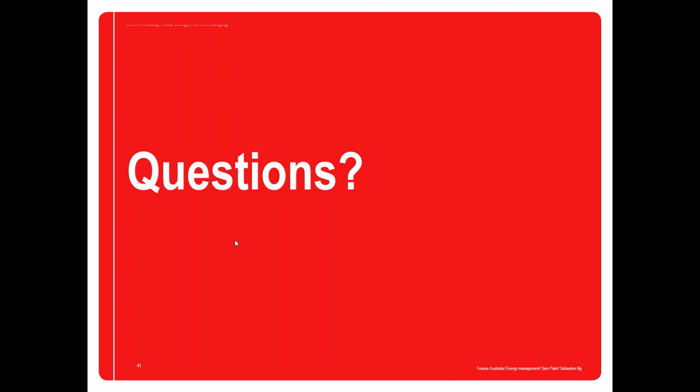It's a really good question, because what's the difference between the energy management functions using a Fronius Datamanager card and the Fronius Ohmpilot? Now, the major difference between those two solutions is that if you're switching the hot water system using the external relay, you will have to wait for a certain power level. For example, we showed you in the presentation that you have to set the threshold for the activation of the relay. So basically, you have to wait until the full amount of energy is being fed to the grid. For example, let's say we set 1200 watts feed-in. That means we'll have to wait until we get 1200 watts of surplus energy from your PV system. And below that, if you're getting only 1000 watts of surplus energy from your PV system, we cannot switch on that relay.